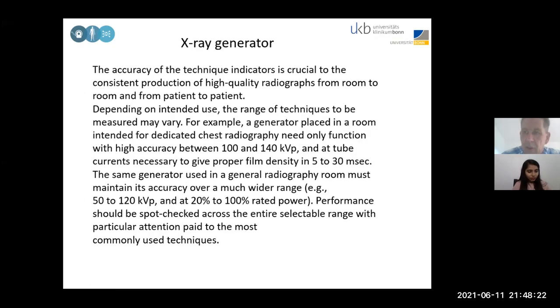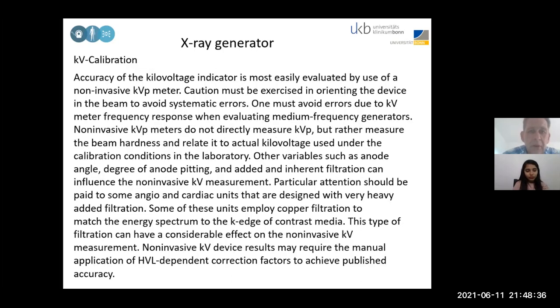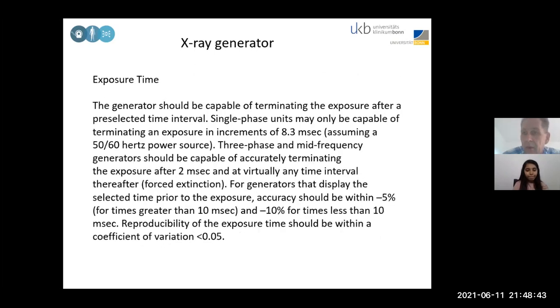Now we come to the X-ray generator. You have to check the linearity of the voltage. So if you increase the voltage, that should be really linear, and it's not 120, it's 118 there. And then you should calibrate that with the voltmeter. You have to check the exposure time.